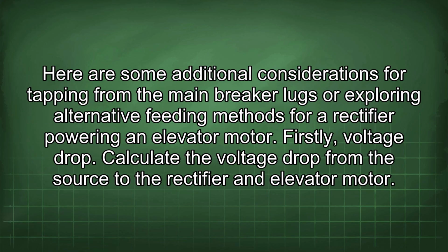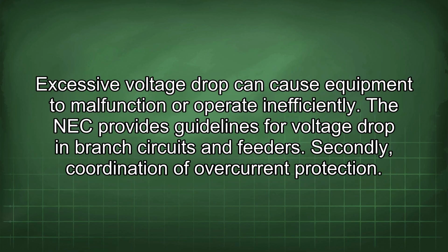Here are some additional considerations for tapping from the main breaker lugs or exploring alternative feeding methods for powering a rectifier for an elevator motor. Firstly, voltage drop. Calculate the voltage drop from the source to the rectifier and elevator motor. Excessive voltage drop can cause equipment to malfunction or operate inefficiently. The NEC provides guidelines for voltage drop in branch circuits and feeders.